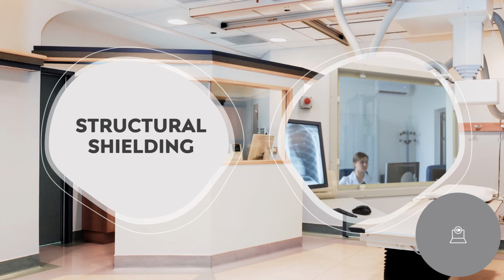The control booth extends 2.1 meters or about 7 feet upward. It should be permanently secured to the floor, and X-rays should scatter 2 times before reaching any area behind that wall. So question, do you think the control booth is considered a primary or secondary barrier? It should be considered a secondary barrier because the X-ray tube should never face the control booth. So when you are positioning your patient, you don't ever want to have to turn your X-ray tube to where it would be facing the control panel or have the beam coming out towards the control panel.